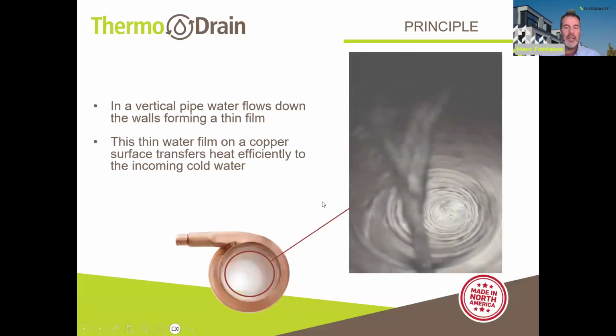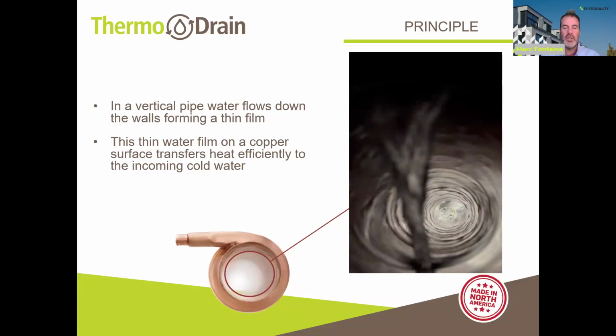The way that this heat exchanger works is that we're able to get pretty high heat transfer efficiencies by having the unit being installed vertically. So this is a top view looking down at a drain pipe where a drain water heat recovery unit is installed. And you can see that as water goes down the drain pipe, it has a tendency to spread around and fill in the whole inside diameter of the pipe instead of falling in the center as one may expect. And so this phenomenon makes for really good contact between the hot water going down the drain and the inner copper tube, and allows for a lot of heat to be transferred across the copper in this fashion. So it's important to note that these devices are meant to be installed vertically. As you install them in another angle or horizontally, they still work, but the performance is reduced significantly.